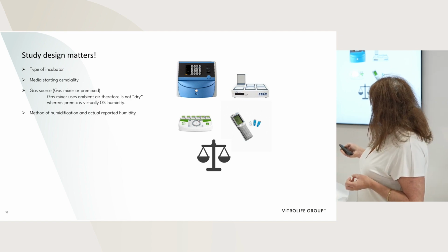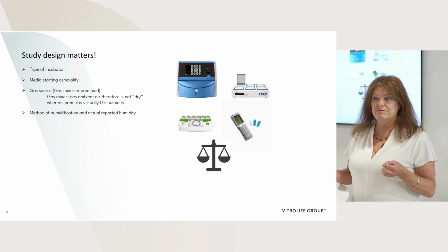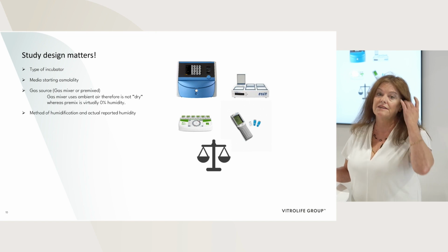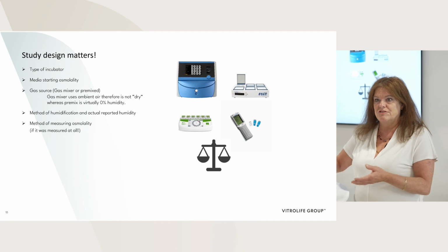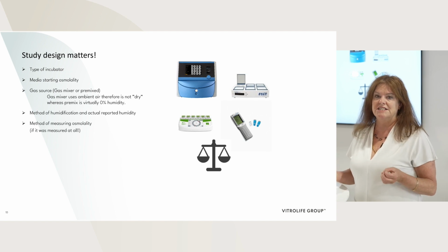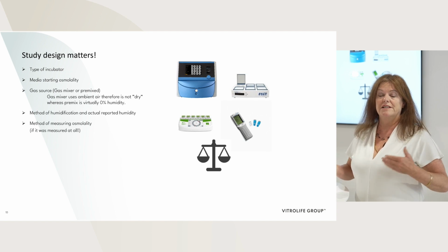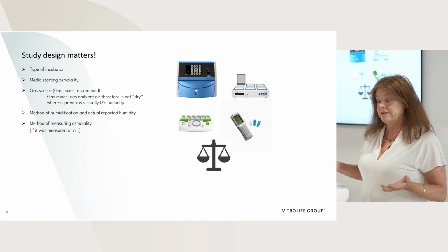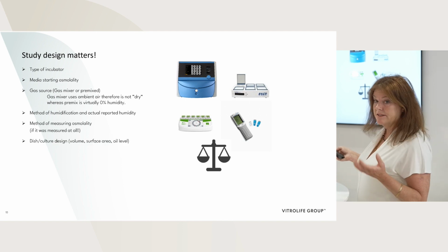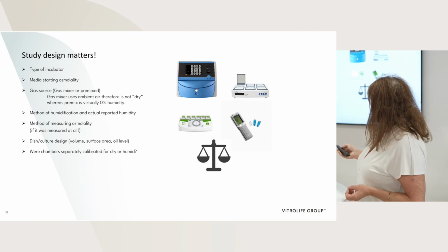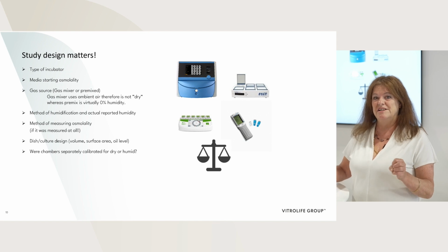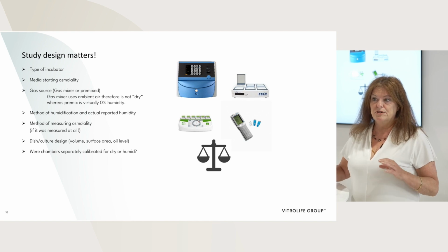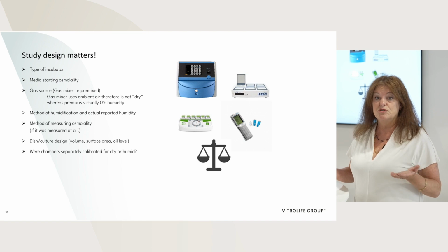And then the method of humidification. I see these studies with humid and dry, and relative humidity is not even reported for these chambers that they claim they've humidified. And in fact, in many studies, they're not even reporting the osmolality. They're just saying dry, not dry, and there's a lot of study details lacking. So they're not universally applicable to all non-humidified or different culture systems. And again, the dish culture, what kind of dish was used, and were the chambers separately calibrated? If you have an instrument, CO2 sensors need to be calibrated for dry or humid. So if you're having a split system, did they also do these calibrations?